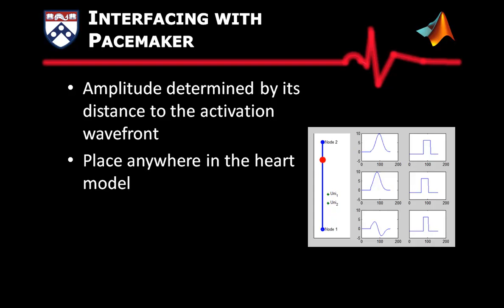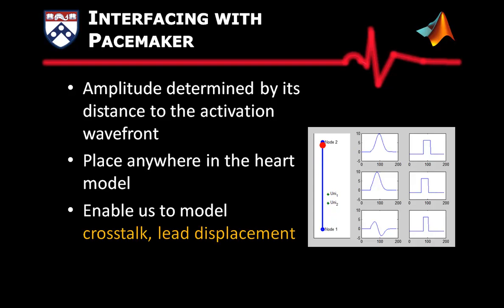When the activation wavefront moves from node 1 to node 2, the probe will sense the electrical activities. The amplitude of the signal is determined by the distance to the activation wavefront. These probe models can be placed anywhere within the heart which enable us to model pacemaker malfunctions like crosstalk and lead displacement.